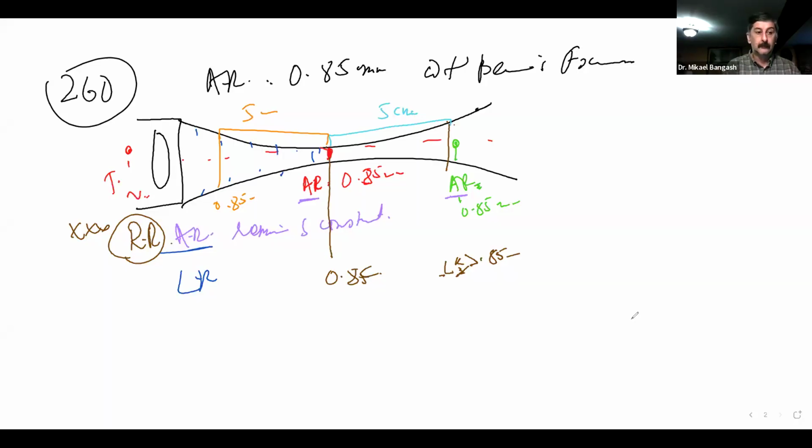Good. So what did that 0.85 millimeters mean here? As long as the distance between two reflectors, shallow and deep, is either equal to 0.85 or greater than 0.85 millimeters, we will have a good resolution.